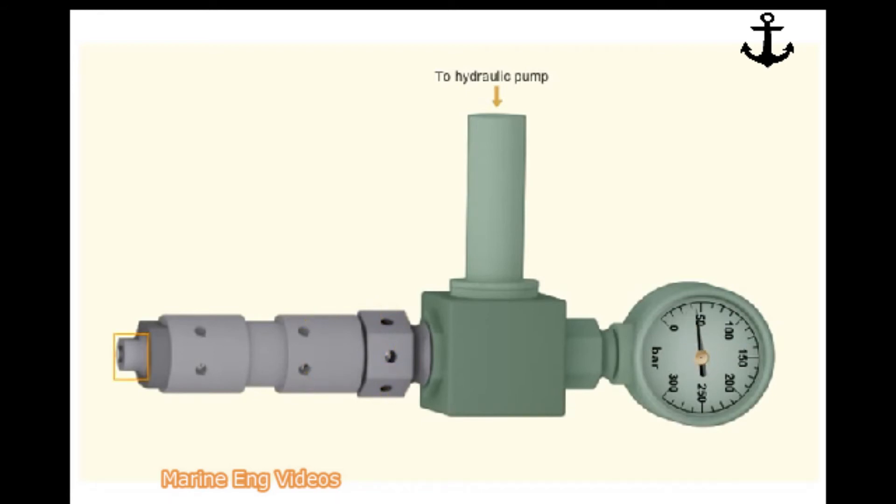Tighten the adjusting screw of the safety valve until the correct pressure is achieved. Tighten the lock nut.